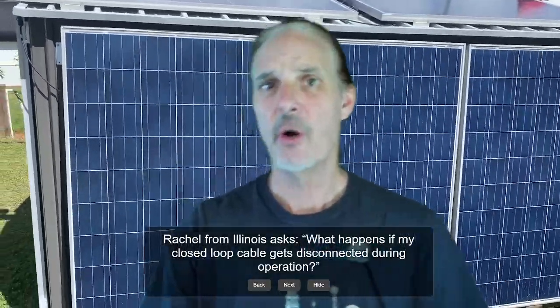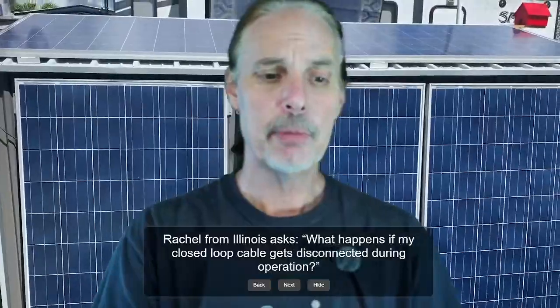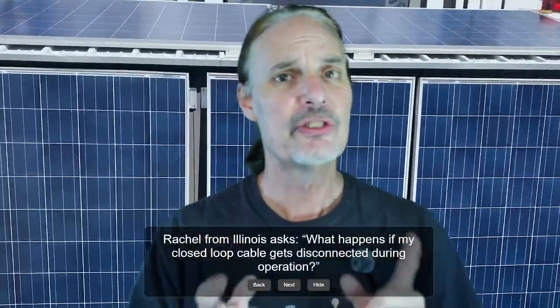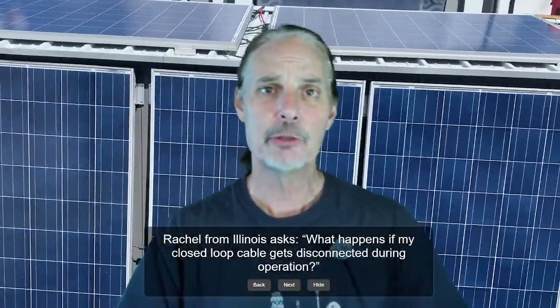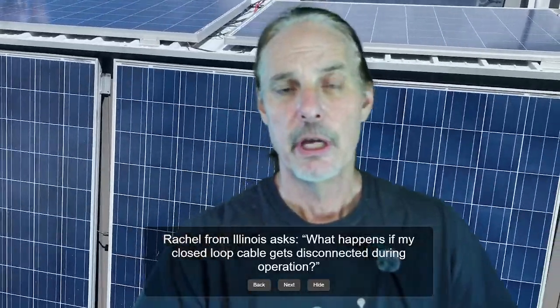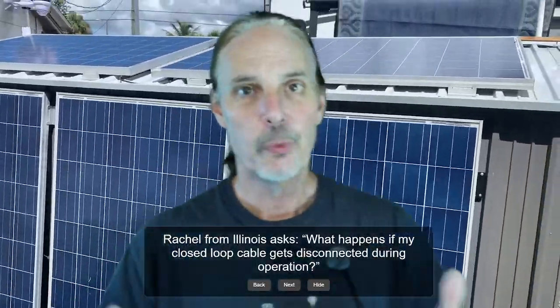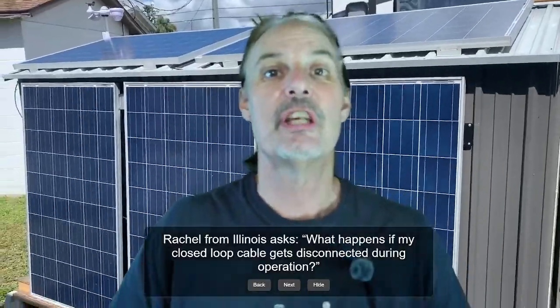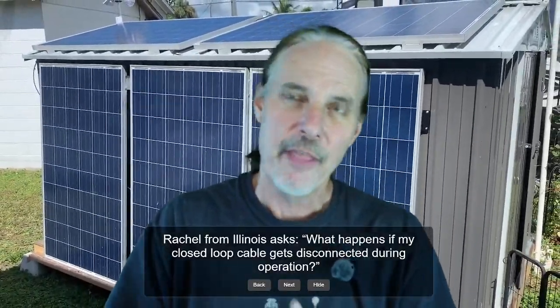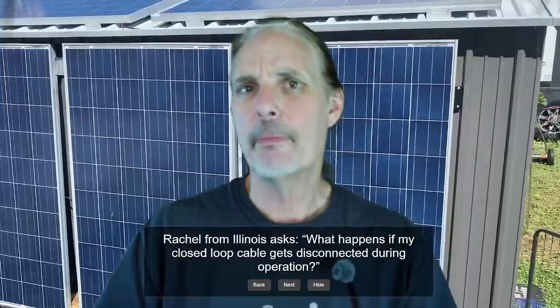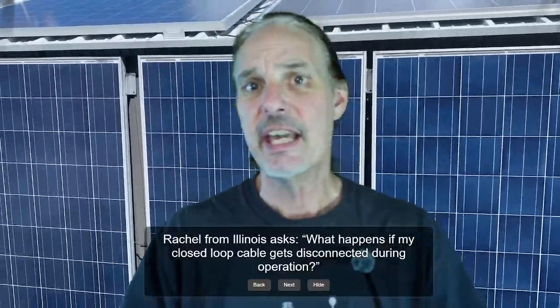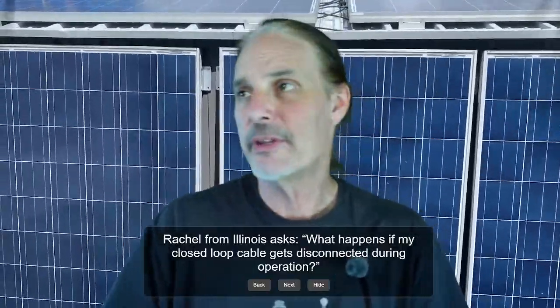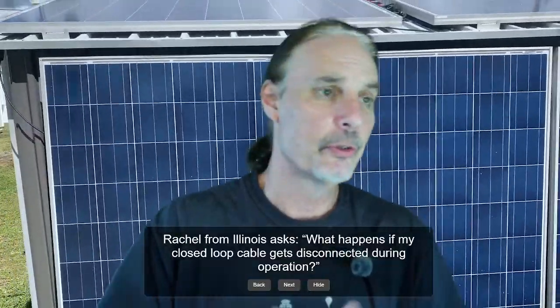When I did so, I unplugged the communication port and plugged it into the solar system, and as soon as the 6000 XP registered that the batteries were gone, it shut down. It no longer ran power because it didn't know the state of the batteries. I thought that was a little strange that there was no backup profile to say, hey, you still have 53.6 or 53.2 volts, whatever it happens to be, go ahead and continue operating in open loop.